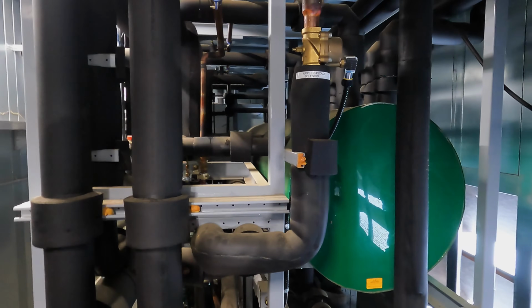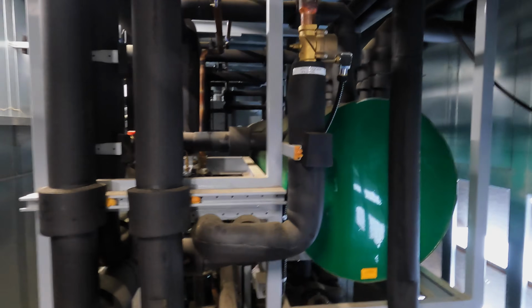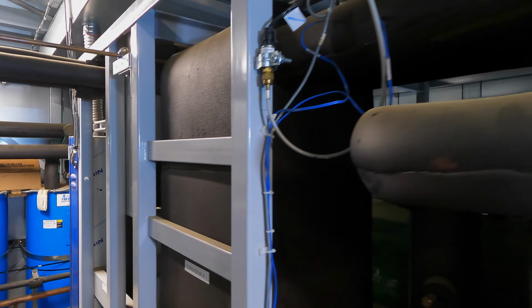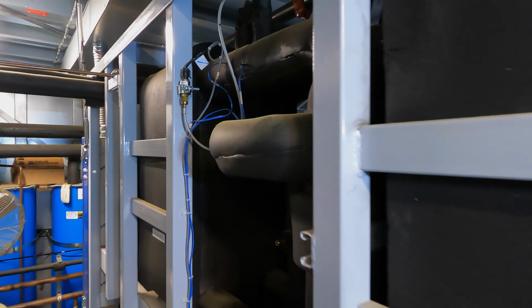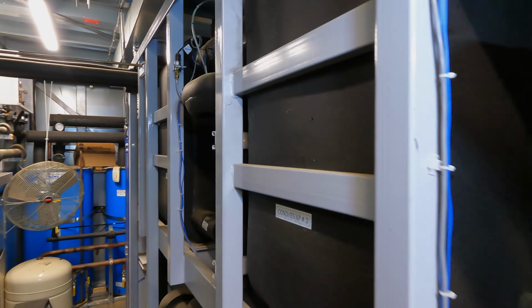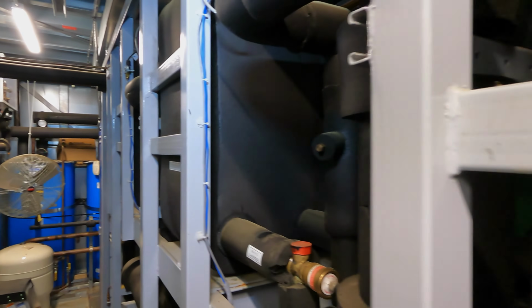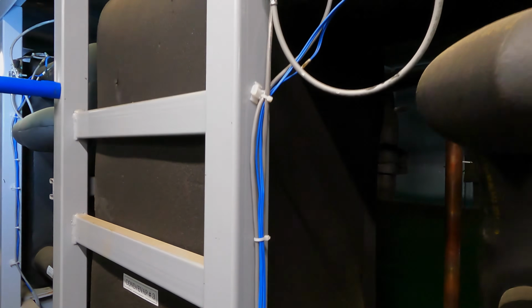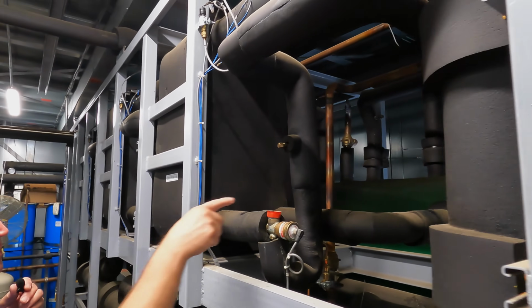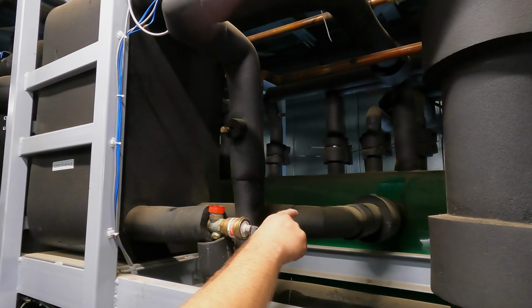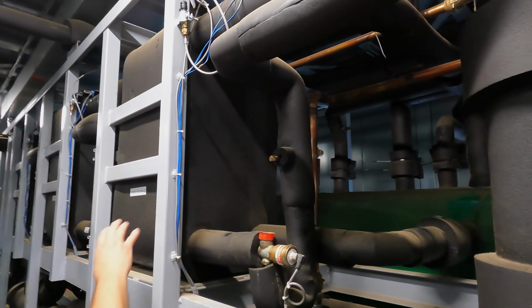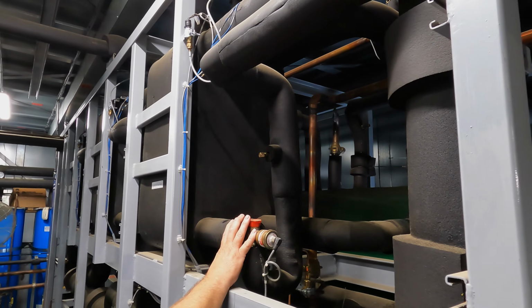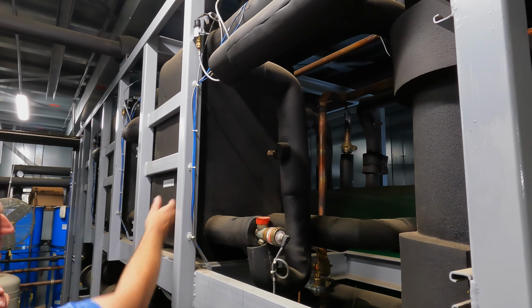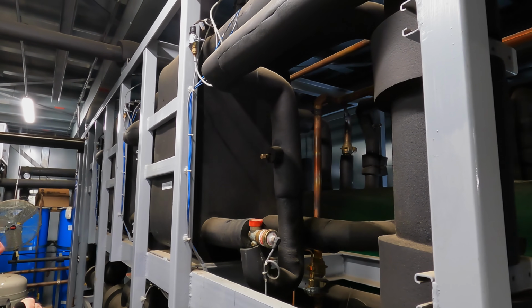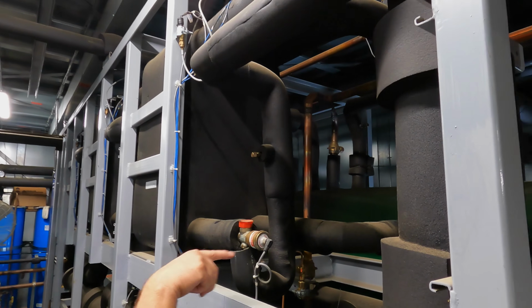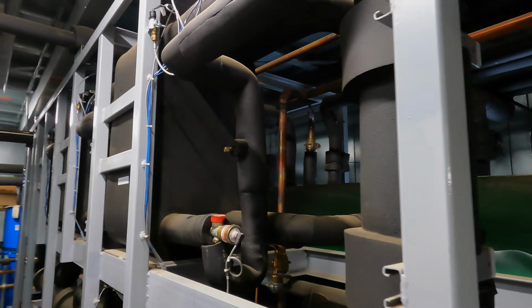Big green vessel, that's what's holding all of our CO2 liquid. And then we have our condenser evaporators. We have 3 of them: 1, 2, 3. And what we do with this is as the CO2 vapor comes off the top of the vessel, it's pulled into this chiller. This side is our 449A liquid refrigerant. We have a plate-to-plate chiller system, and basically it's taking that vapor and turning it into a CO2 liquid.